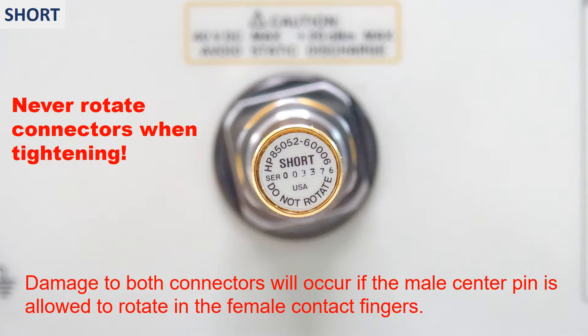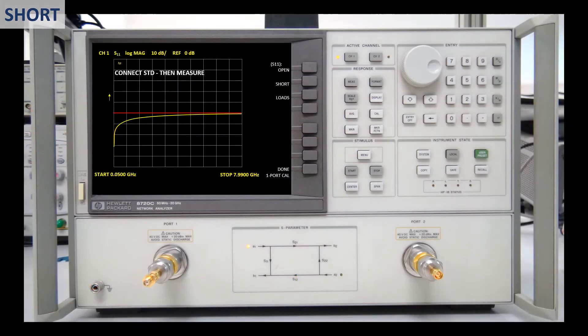The connection of the standards is a critical step. High frequency connectors must be handled with care. A damaged connector can damage other connectors. After connecting the standard, I press Short and the instrument starts the first measurement. After the measurement, the label Short becomes underlined.